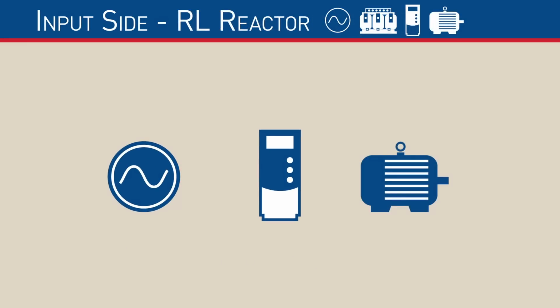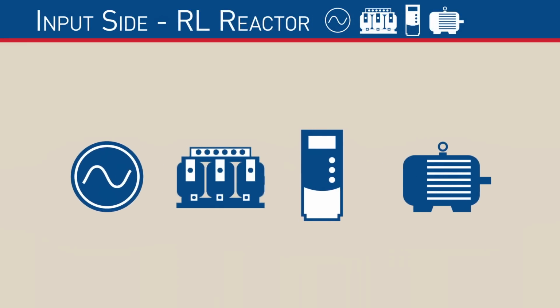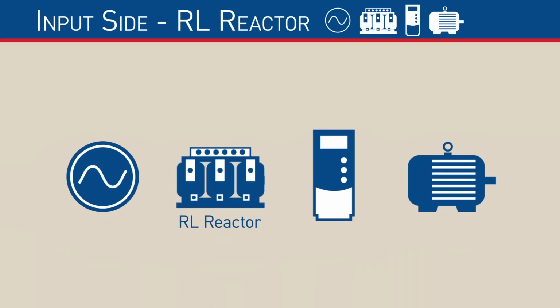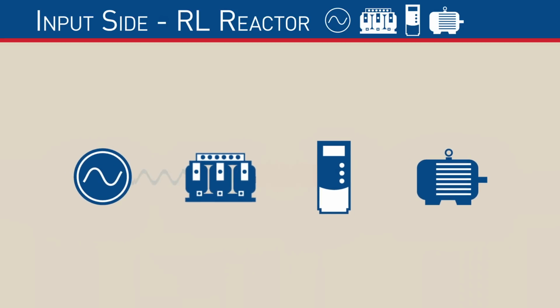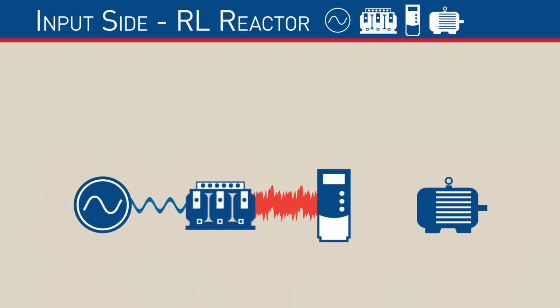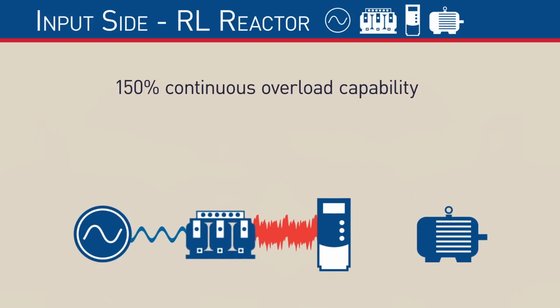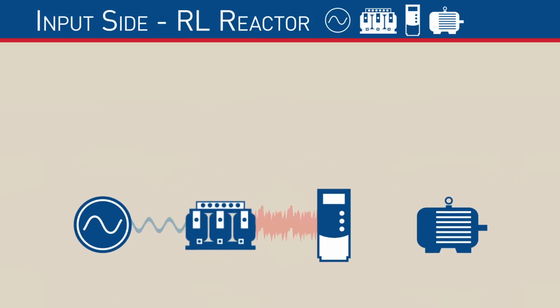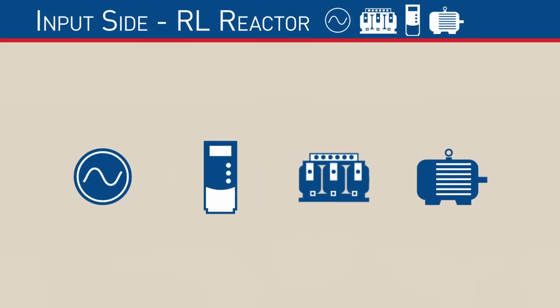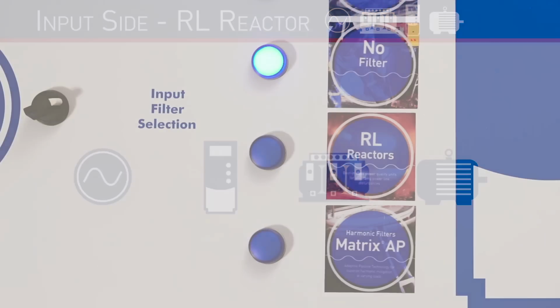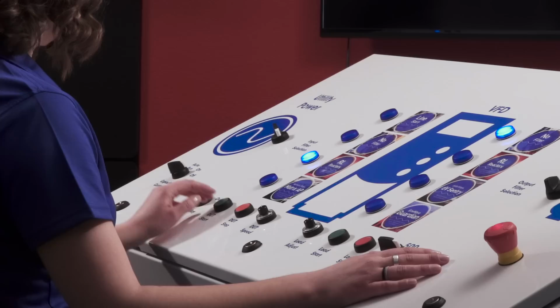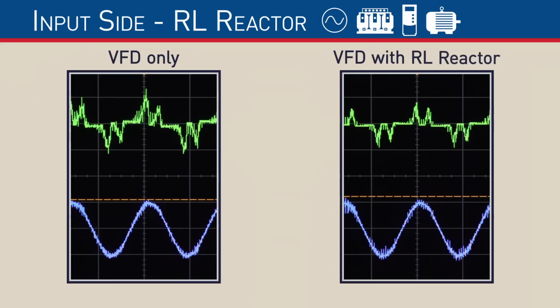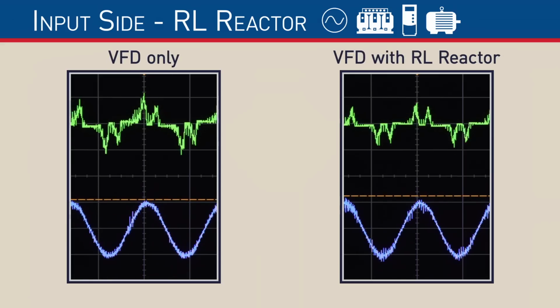In order to bring these harmonics down to an acceptable level, we can introduce MTE's RL Reactor at the input side of the VFD. The RL Reactor is a very robust product that offers 150% continuous overload capability with low watt loss. This same reactor can also be used on the output side of the drive without any derating. As we bring the RL Reactor online, we can immediately see the effect it has on the current distortion by the reduction in intensity of the current spikes.